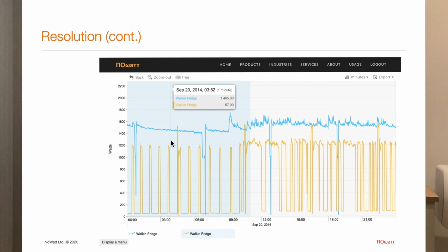But being able to look at the signature tells me a lot about how the actual refrigerator is using energy. If you look at the orange one, you can see that the compressor, the big thing in the actual fridge, is going on and off. And of course, it will go on and off according to the temperature. When it goes on, it will cool the refrigerator such that it hits a bottom set point and the pump will go off, and so on. And that's great. But the blue refrigerator, that's using 5 times more electricity, is only ever dipping off once every 6 hours, and in fact that's when the defrost heater comes on. So in fact it's running all the time, which tells me that it's never reaching temperature. So being able to actually see the pattern tells you a lot.